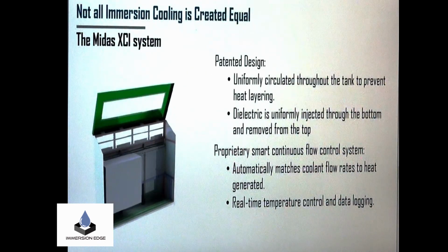Not all immersion cooling is created equal. Our Midas XCI technology is patented since 2011. The dielectric is uniformly circulated throughout the tank to prevent heat layering, injected through the bottom and removed from the top. There's a proprietary smart continuous flow control system with real-time temperature control and data logging, and that's really important. We work with Modius, and that is a great product for that.